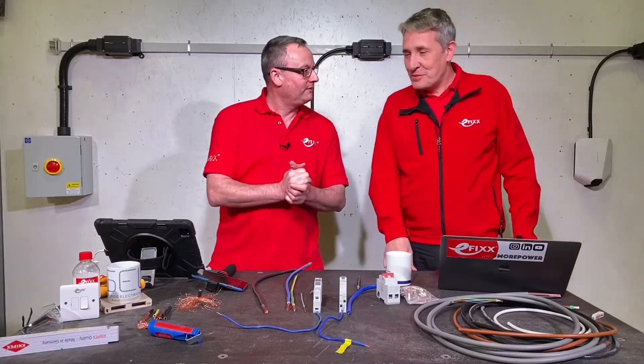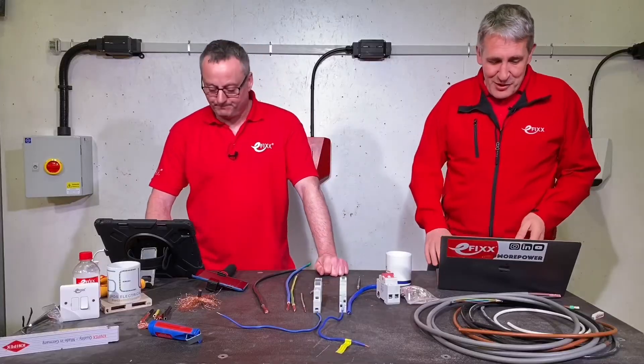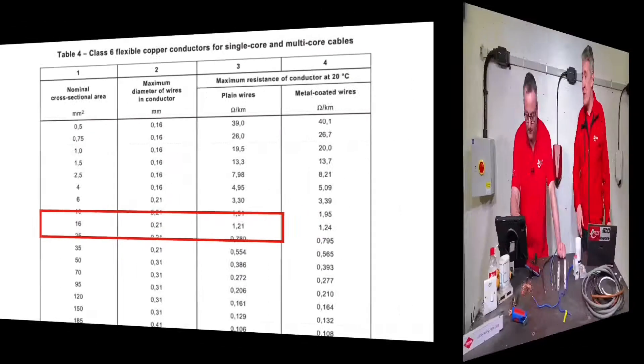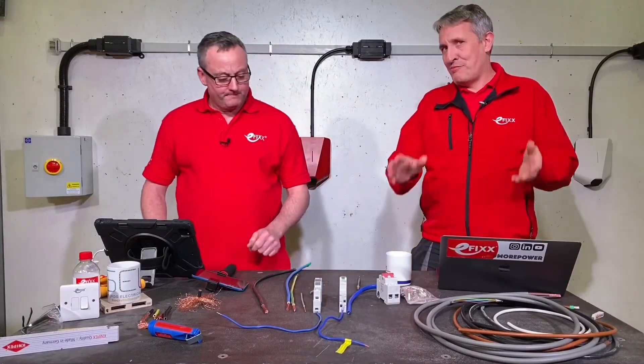If we return to our standard, for that 16mm class 6 conductor the maximum strand diameter is 0.21mm each. Again, it doesn't define how many strands make up that conductor, but it does define the maximum resistance.